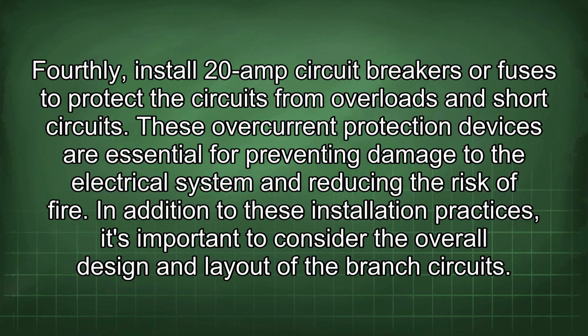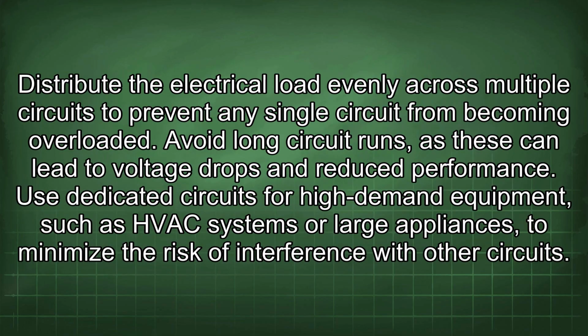In addition to these installation practices, it's important to consider the overall design and layout of the branch circuits. Distribute the electrical load evenly across multiple circuits to prevent any single circuit from becoming overloaded. Avoid long circuit runs, as these can lead to voltage drops and reduced performance.